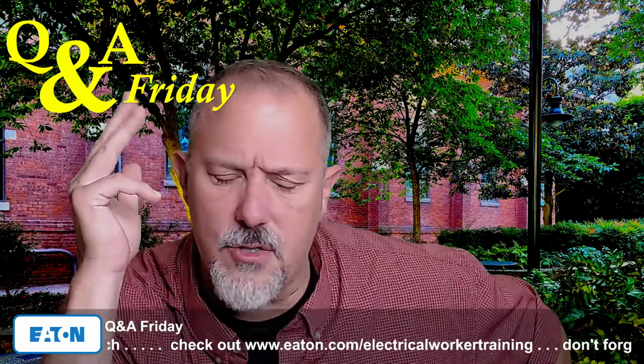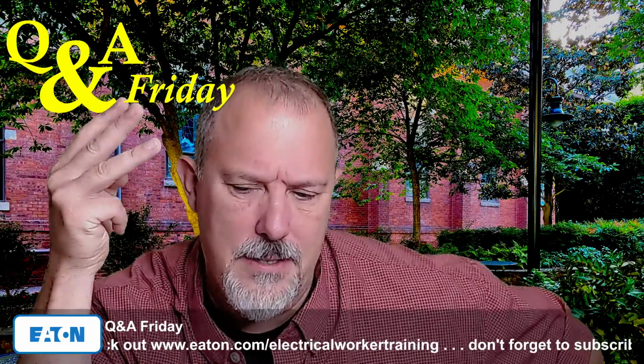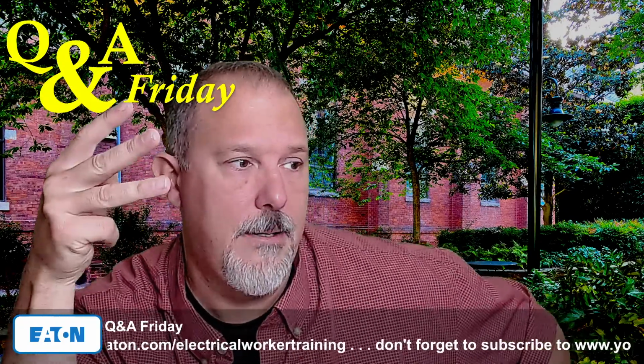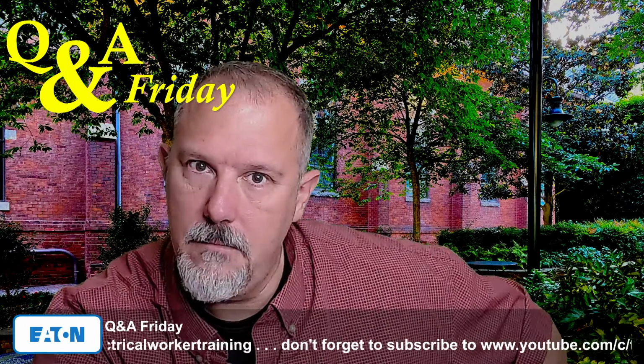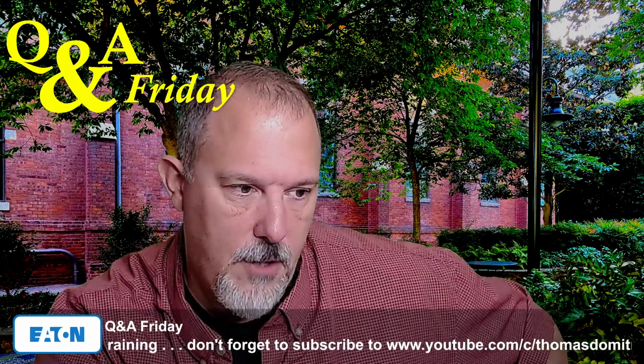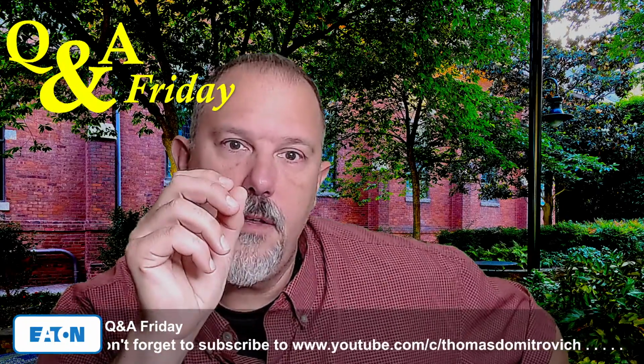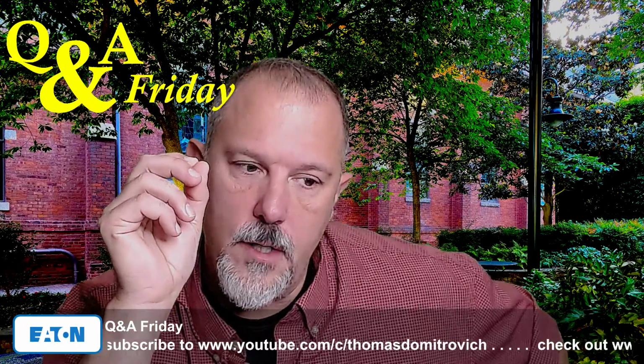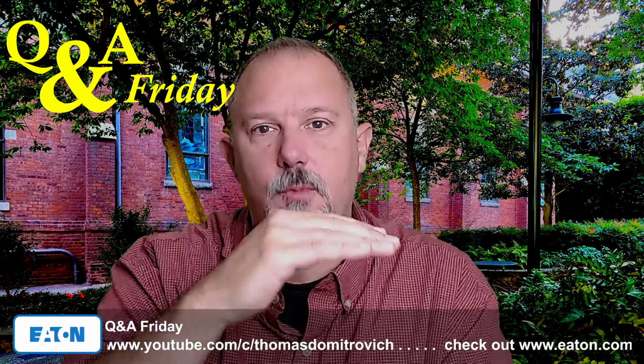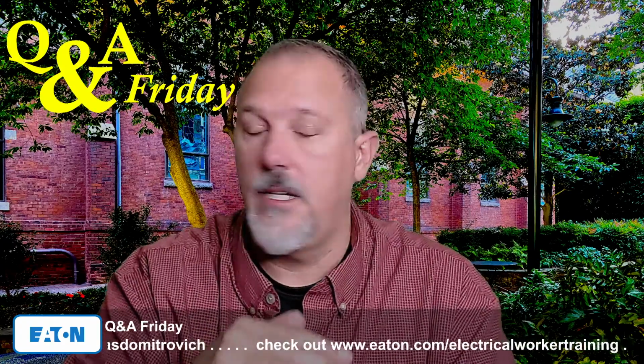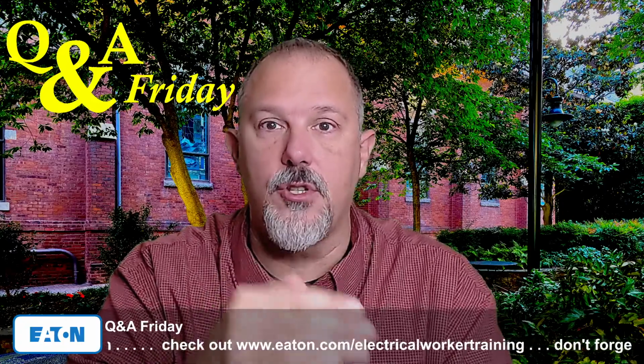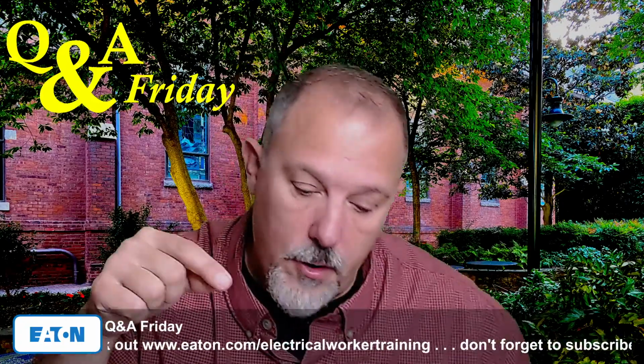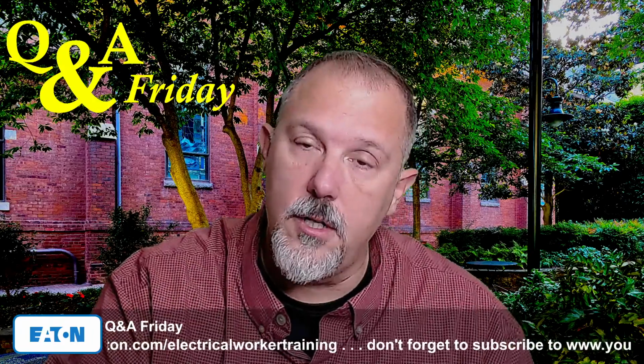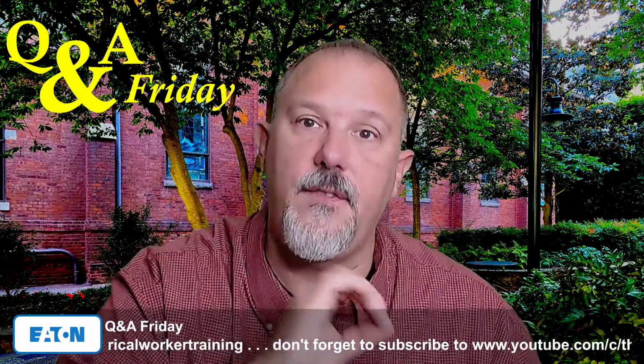If we tell you, for example, motor control centers, I believe, are 3-cycle devices. Could be 4, but I believe they're 3. I could stand to be corrected, and if anybody out there knows, please do so. The fact that I can have a piece of equipment that's rated for, say, 3 cycles at its bolted fault current value tells me that I'm testing it at 3 cycles. All of my terminations, as long as you're following my rules with regard to torque, then you will have a good, safe, solid installation.